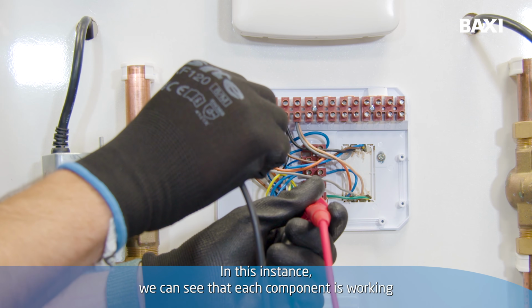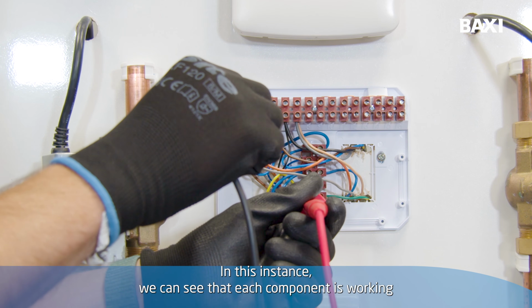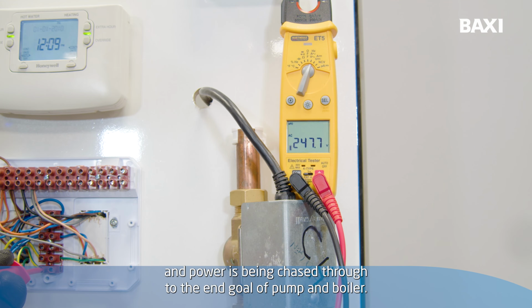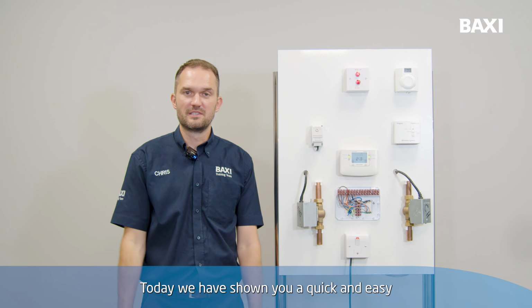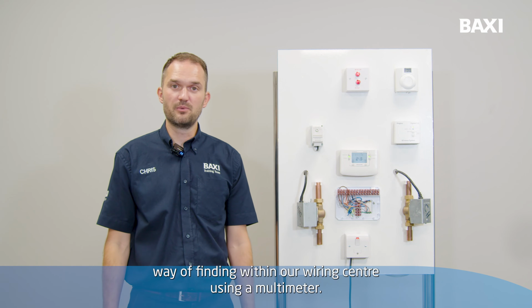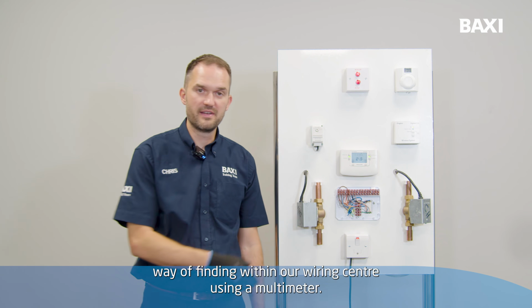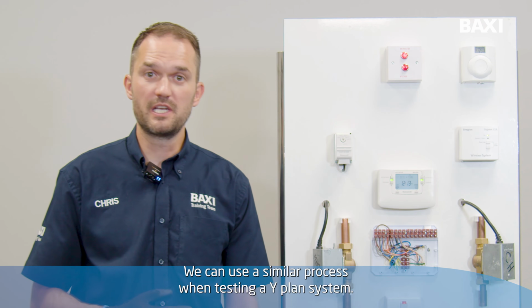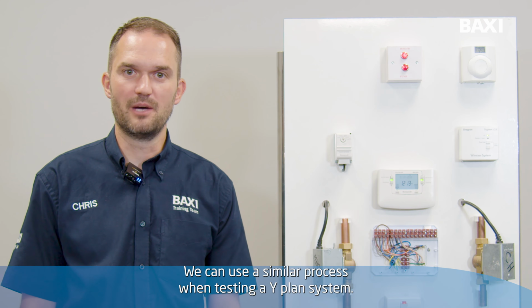In this instance, we can see that each component is working and power is being chased through to the end goal of pump and boiler. Today we have shown you a quick and easy way of fault finding within our wiring centre using a multimeter. We can use a similar process when testing a Y plan system.